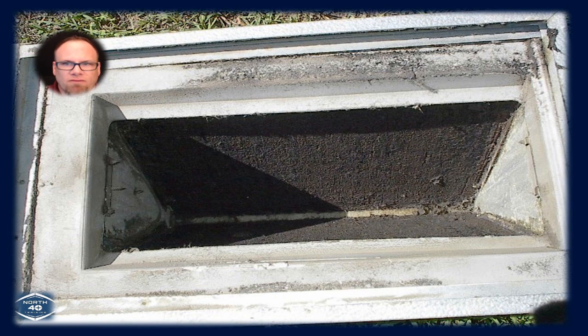Well, it couldn't get rid of the airflow. And that's a big problem. When you can't get rid of the airflow, you can't get rid of the heat. So you've got to think about those things when you're out there. Think about how quickly this problem could have been solved during that installation. Now, sure, it might slow you down for 10, 15 minutes while you clean this thing out, but that's not nearly the amount of time that was spent afterwards in the several trips, and also getting the technical department and almost the manufacturer involved with the situation, and getting egg on your face, because in reality, the problem was yours, not the equipment at all.